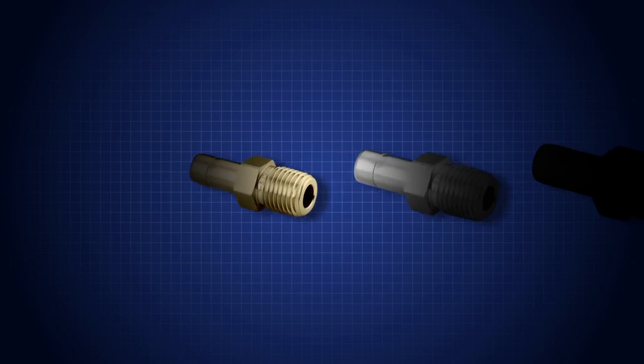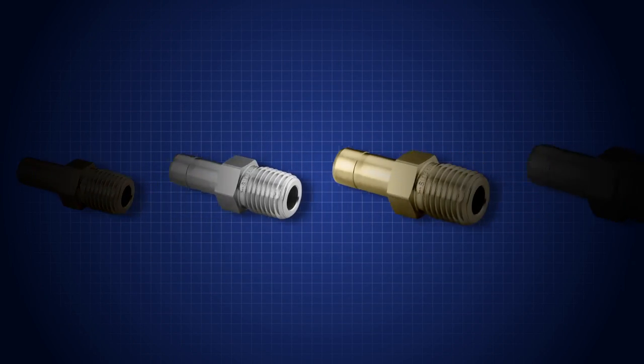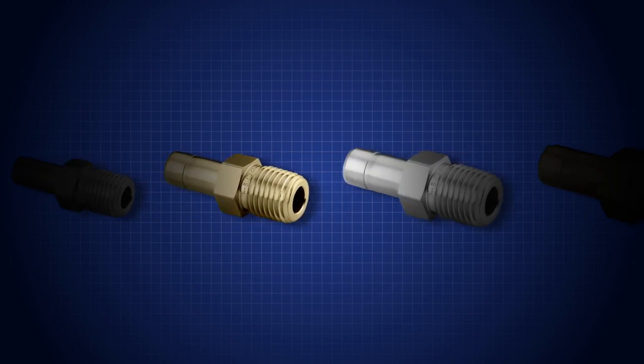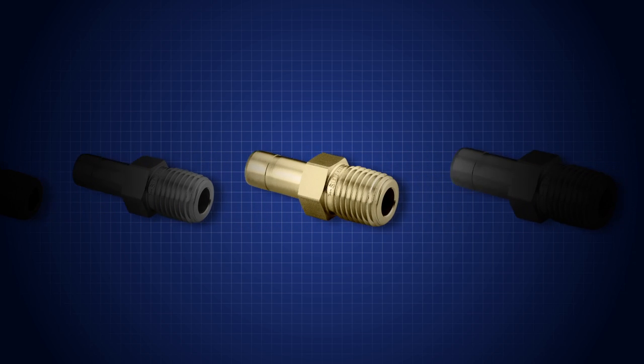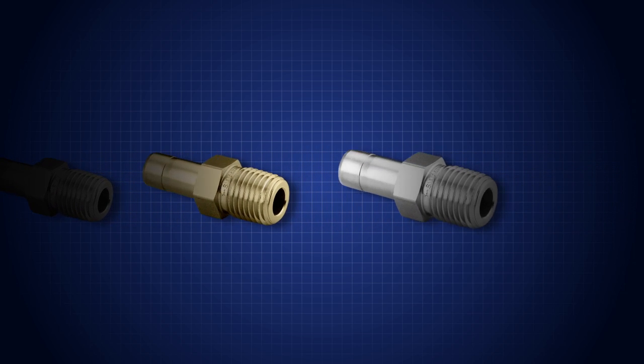For one-sixteenth, one-eighth, and three-sixteenth inch, and two, three, and four millimeter tube fittings, tighten the nut three-quarters turn to the nine o'clock position.